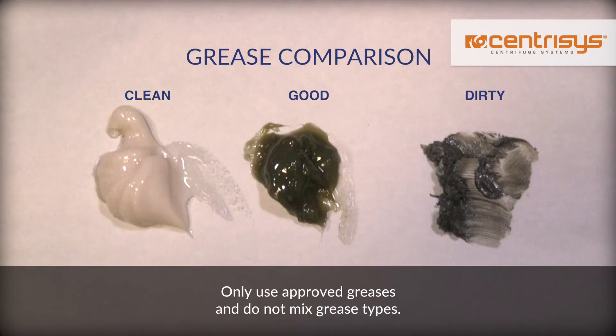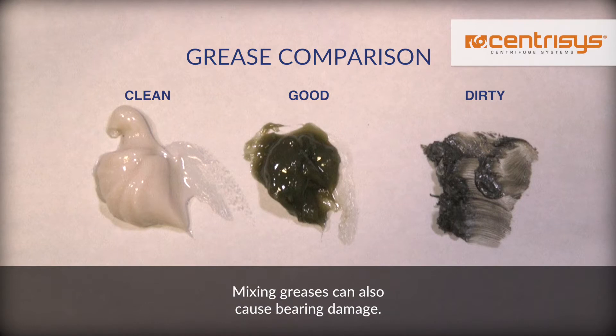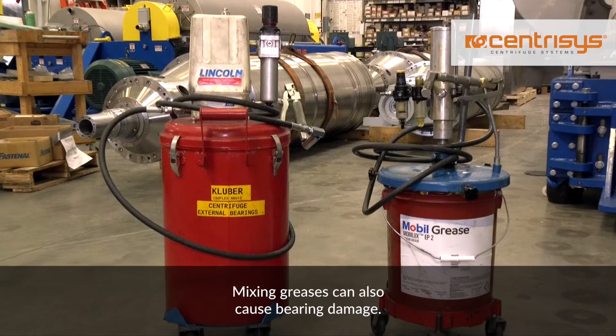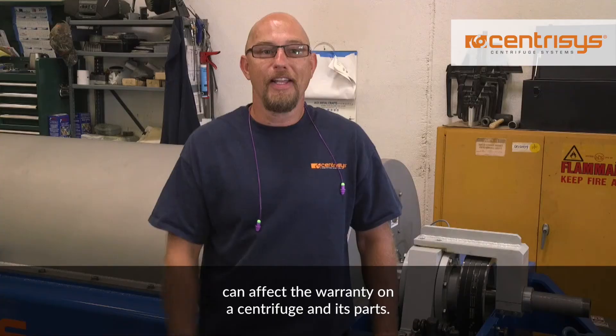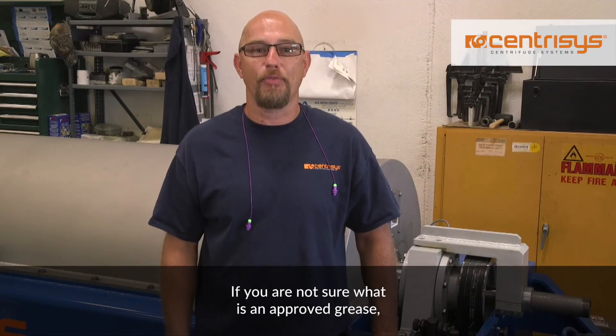Only use approved greases and do not mix grease types. Mixing greases can also cause bearing damage. Be advised that non-approved lubricants can affect the warranty on a centrifuge and its parts.